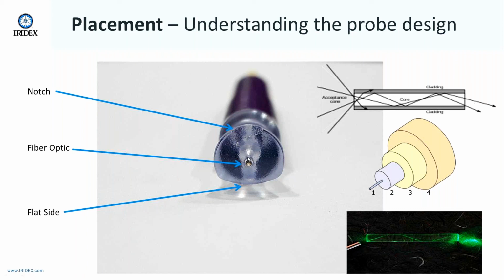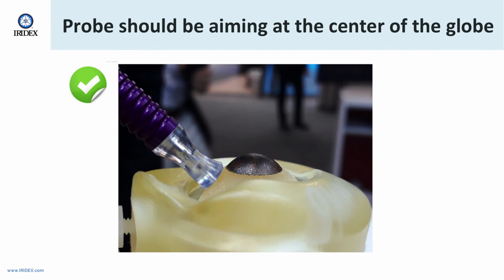of the probe. Because this fiber and insulation has been changed by producing this bubble probe, it is essential that it is in a liquid interface to deliver and couple all of that energy into the tissue that you desire to treat. If you are not in a liquid interface, this energy will disperse up to 50% sideways coming out of the probe as opposed to being delivered where it's desired. It's also imperative to know that this 2/3 offset helps to position the probe over the ciliary body for the treatment as opposed to moving it closer to the limbus. So if you orient it with the flat side toward the limbus, you are going to be treating in undesirable areas of the eye. The probe should be aimed towards the center of the globe.